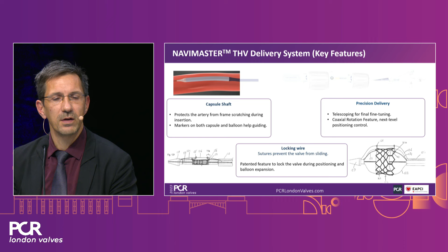And there are special features on the backside of the catheter that help you to fine-tune the position of the valve and to rotate the valve into the correct position. The valve, when it comes out of the sheath, is covered by a capsule. This is intended to avoid any interaction between the valve frame and the aorta, and avoid scratching of sclerotic material and pushing it up all the way to the ascending aorta. There's a telescoping knob at the end for fine-tuning of valve depth, and there's a rotational feature at the end to allow for anatomical positioning. In addition, there's a locking wire that prevents the valve from diving during implantation.